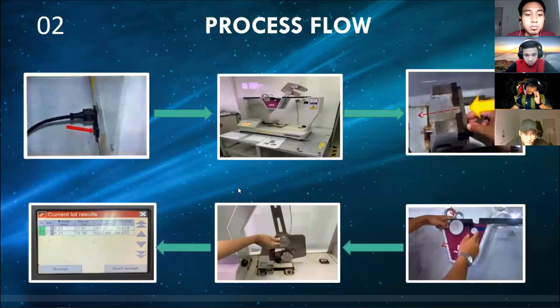Next, moving on to the process flow. First, we must start up the machine and switch on the button. Then we perform the calibration process. After that, for the second process, we position the hammer to its release position and lock the hammer. After that, we place the specimen onto the support span where the notch is in the center position, as referred to in the picture. Moving on, we press the safety lever and release the knob to let the hammer impact the specimen, and then we get the result of the test.